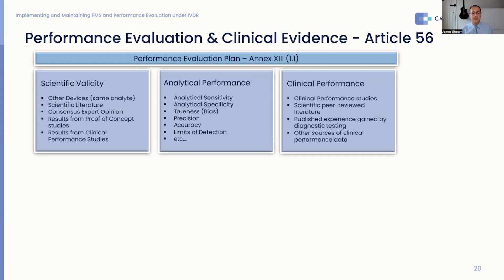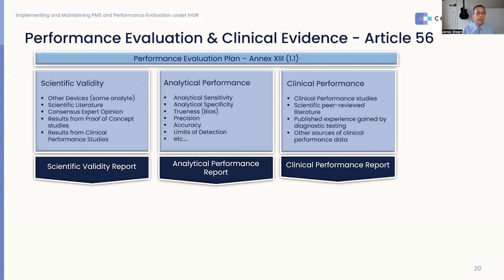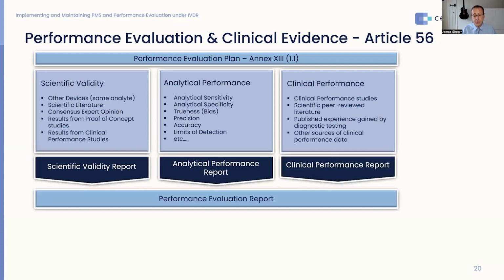So we have the scientific validity, which is the association of the analyte with the clinical condition or physiological state. We have the analytical performance, which means the ability of the device to correctly detect or measure the particular analyte. And then we have the clinical performance, which means the ability of the device to yield results that correlate with a particular clinical condition or physiological or pathological state. All of those reports, the three deliverables there, then go into the performance evaluation report.